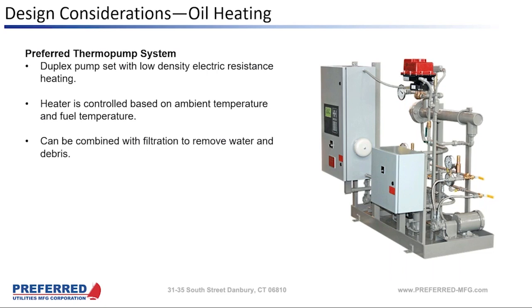And the sequence of operations that you described, David, I think is really good because what that allows it to do is, number one, preempt. If we're using an outdoor air temperature sensor, we're not waiting for the fuel in that tank to get down to a certain temperature, but we already know that it's cold outside, right? And the second thing is it allows really two modes of operation. It allows a mode of operation where we're using maybe the thermal mass of the piping inside the building to gently raise the temperature of that fuel initially, and then as that cold soaks into the tank or the piping, we're bringing on that heater later on.